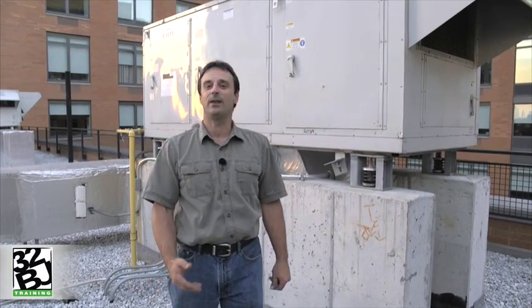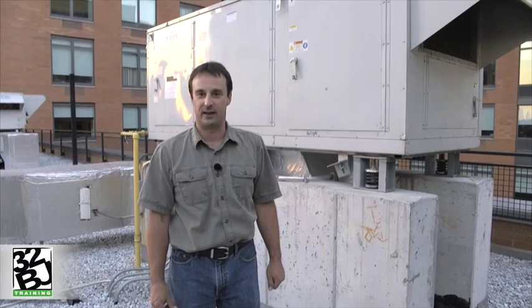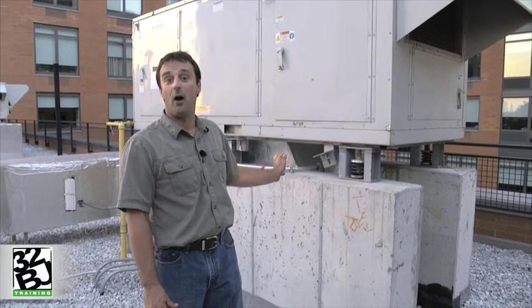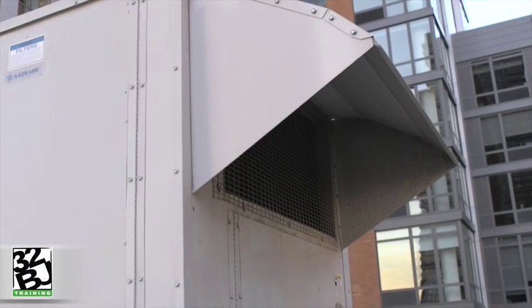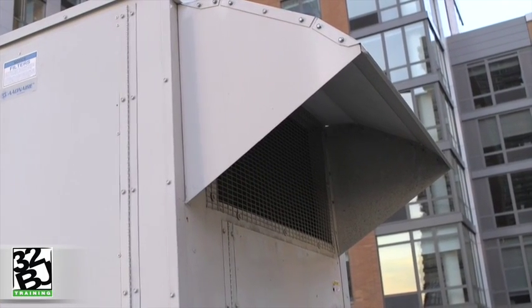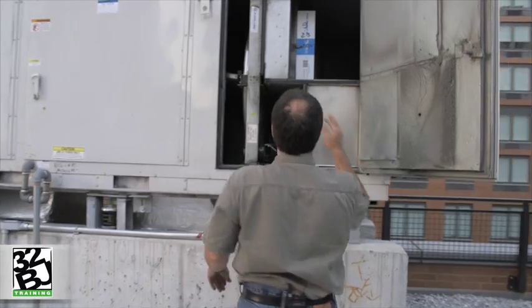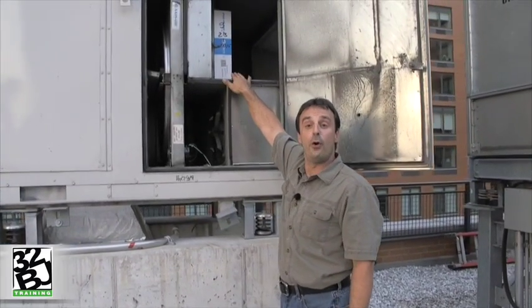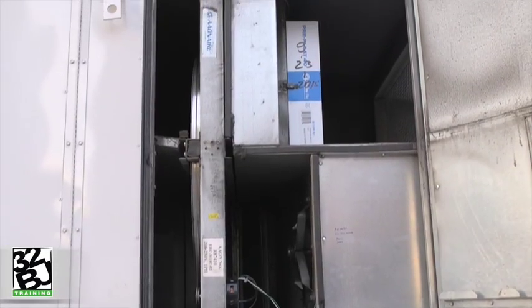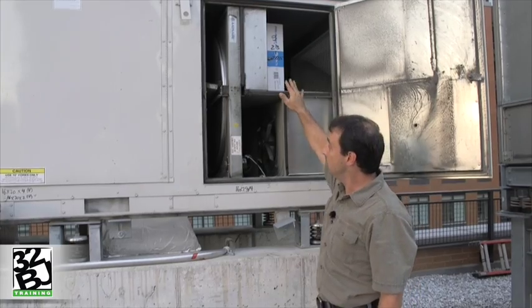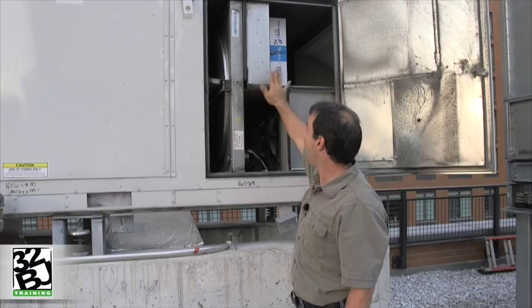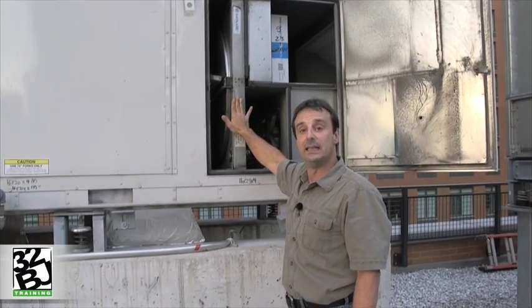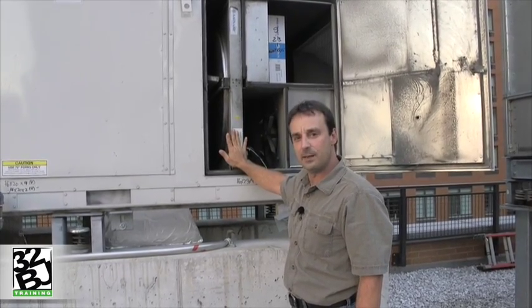Let's take a look at how the air passes through our hallway ventilator. The fan on the hallway ventilator drags in fresh air through the fresh air hood. That air enters and immediately passes through a 4-inch pleated filter to take out the particulates, and this particular machine has an energy recovery wheel, and this filter is to keep that wheel clean. We'll get back to this in a moment.